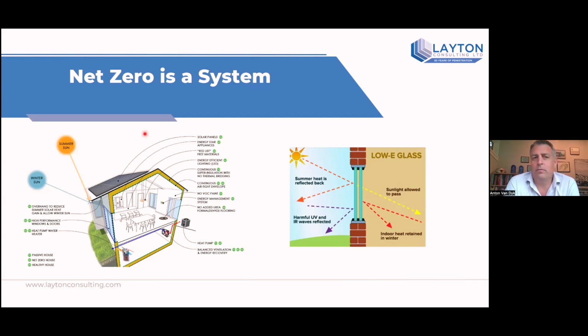And I said, what's the window to wall ratio? He goes, well, what do you mean? We get down to it and he says, yeah, it's about 30, 35 - it was up there, quite high. I said, take 6 inches off the window on both sides and see what happens. So he made the windows a little smaller, which adds wall insulation. And sure enough, it started to change the calculation where the U value requirement of the windows started to drop, because he basically had more opaque wall area that had a better R value.